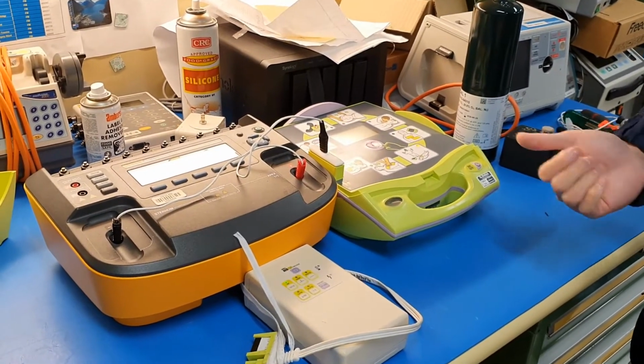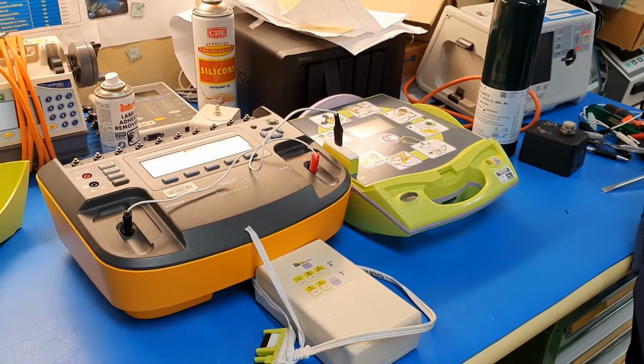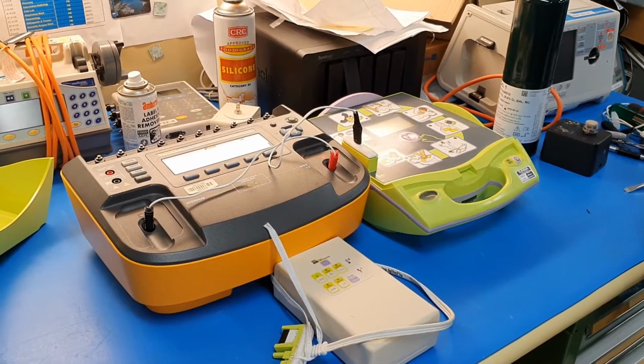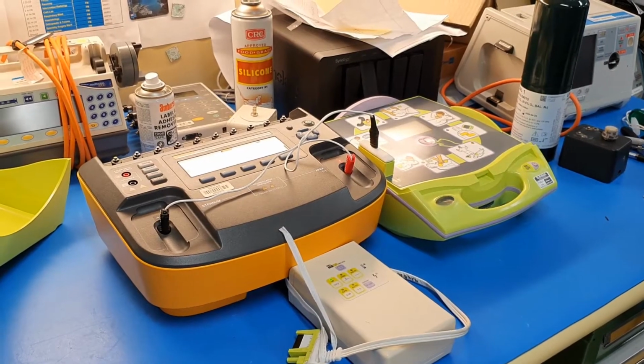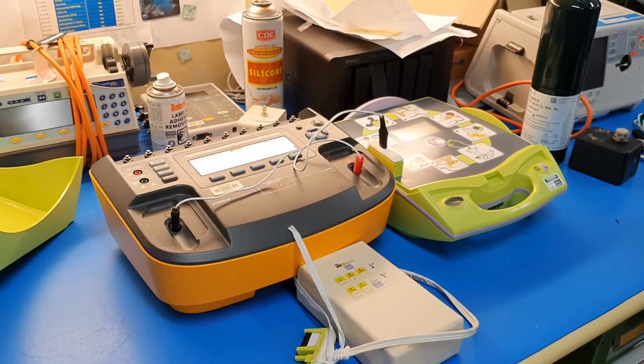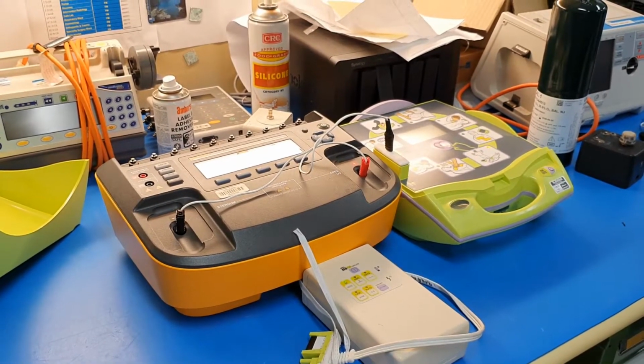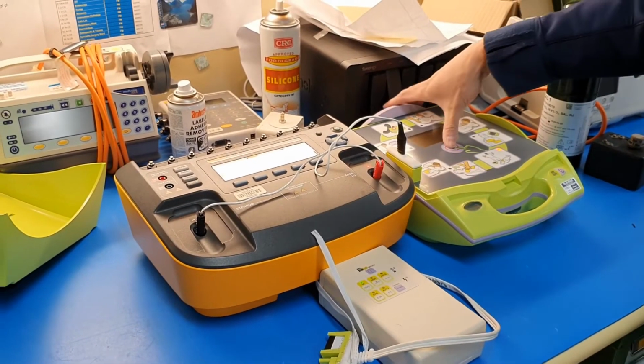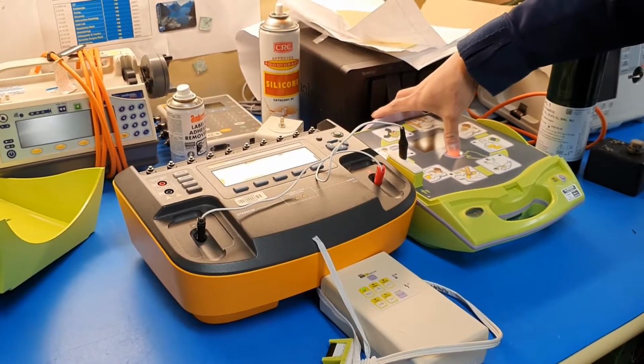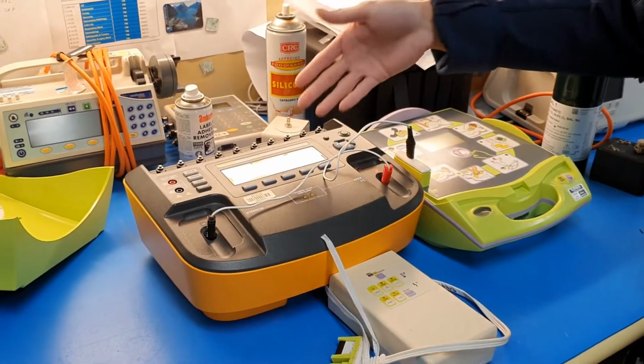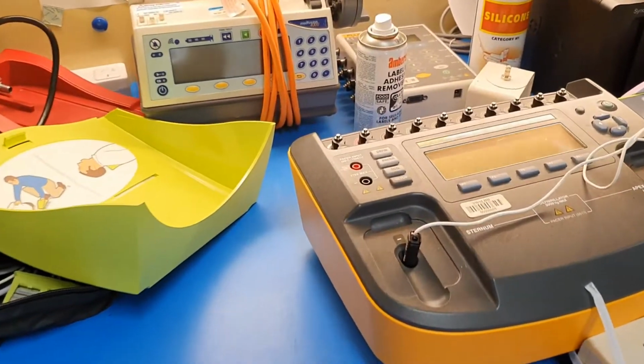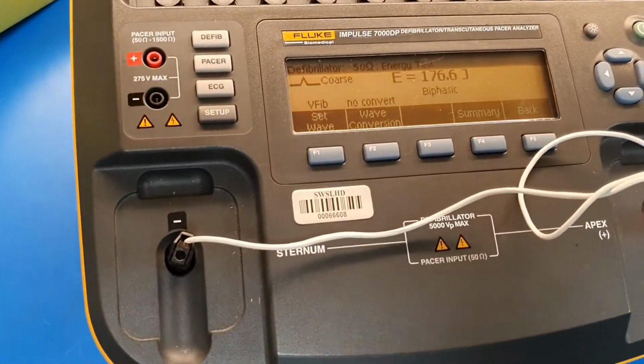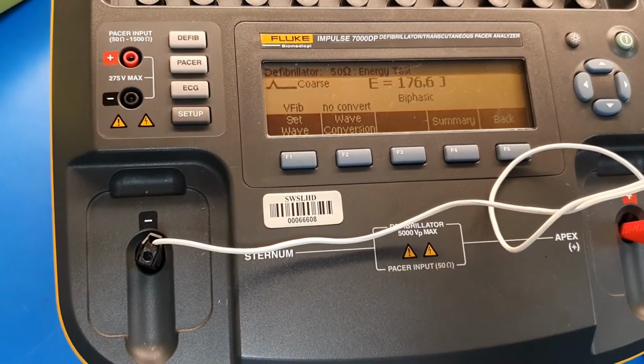So here it's analysing the patient. Analyzing. Don't touch patient. Analyzing. Shock advised. So to determine that the patient needs a shock, press the flashing Shock button. Shock delivered. And you can see the tester picks up what is the shock level. So usually it will be around 200 joules, and there'll be a bit of a tolerance around it.